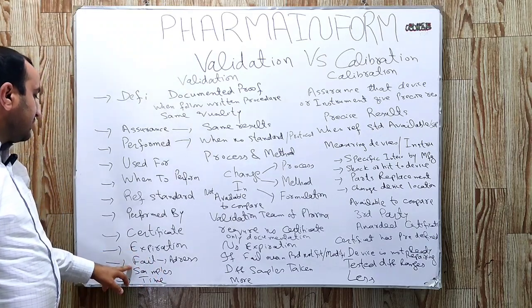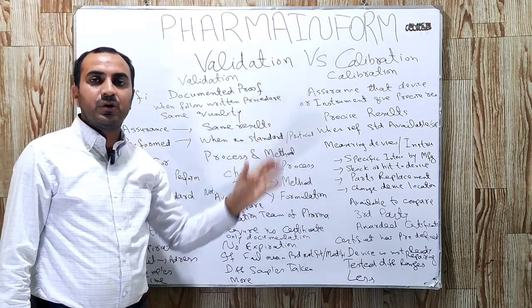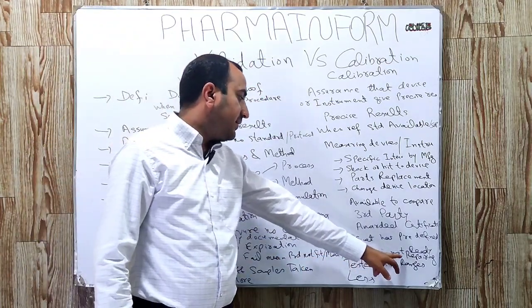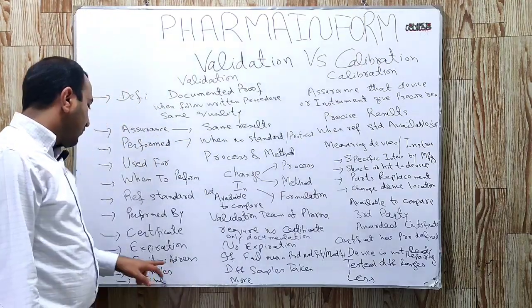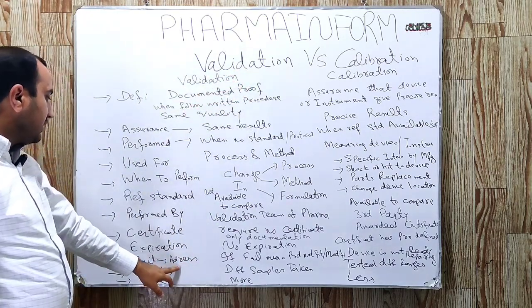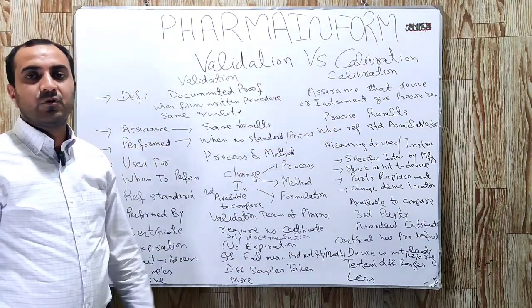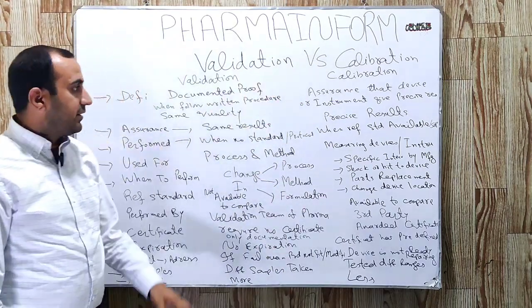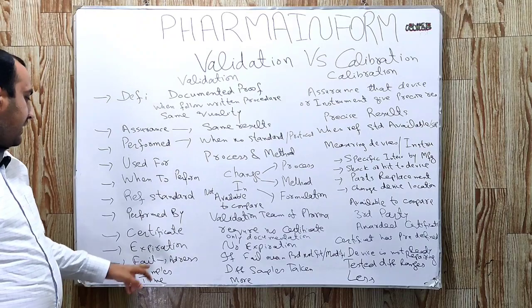Regarding failure: if validation fails, it means the product is not fit for use. If calibration fails, it means the device is not ready or okay to use. In case of validation failure, we make modifications and then perform validation again. In case of calibration failure, we perform repairing.